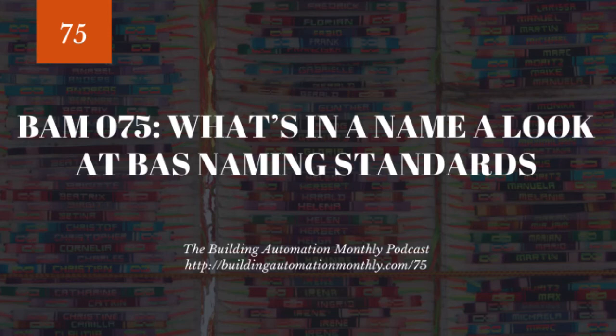So where I'm going with this is that if you look and you're like, man, there's just too much stuff to do, don't do that. Don't look at it as all or nothing. Just look at a piece. Maybe you start by standardizing your point names. I'm going to call everything zone temp, and you start changing those. I'm going to call everything discharge air temp, and you start changing those. And you document it, and you just gradually work your way through.